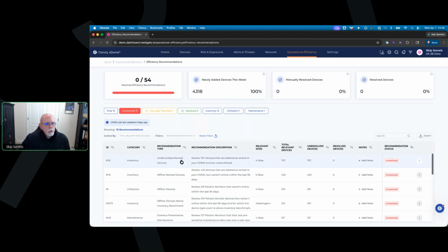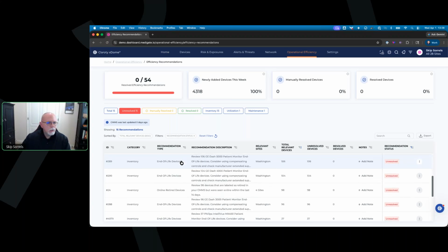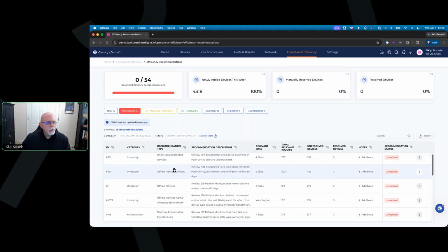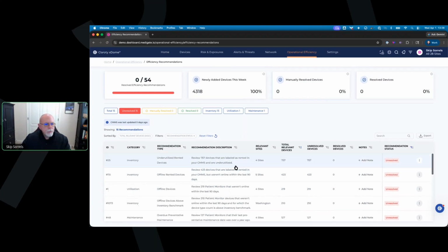We can drill into the device type from that first screen, rather than jumping around, and get to an inventory of devices that fall into different recommendation types, but they're all grouped by device type. In this case we have end of life, located lost - going back to my 'cannot locate' representation - devices that are offline, devices above inventory possibly indicating an opportunity to reduce the fleet of that particular device in that location, and the recommendations that go with it. There are 757 devices labeled as rented in the CMMS that are underutilized.